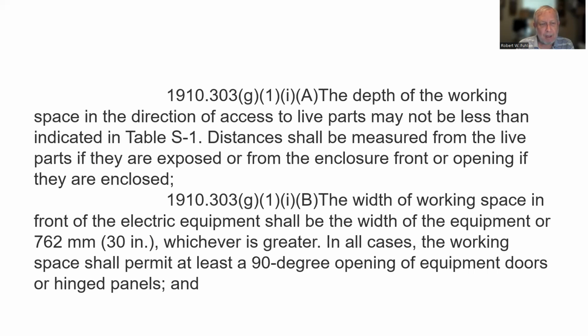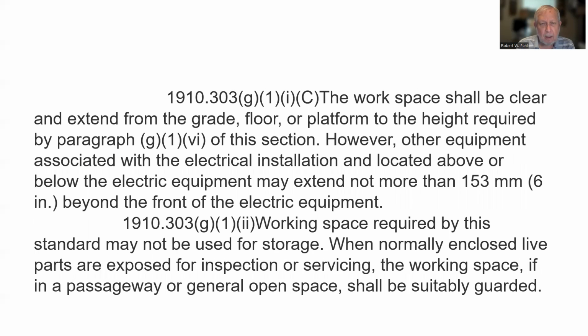The width of the working space in front of the electric equipment shall be the width of the equipment or 30 inches, whichever is greater. In all cases, the working space shall permit at least the 90-degree opening of equipment doors or hinged panels, and the workspace shall be clear and extend from the grade, floor, or platform to the height required by paragraph G1 VI, section, which we haven't got there yet.